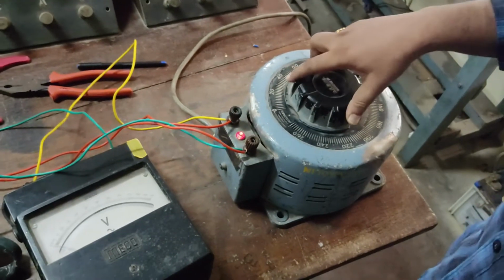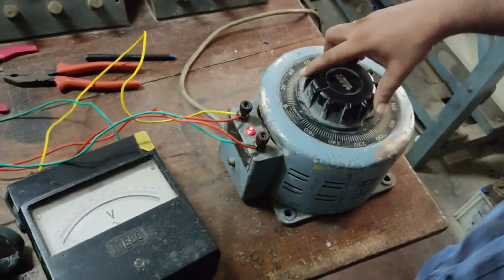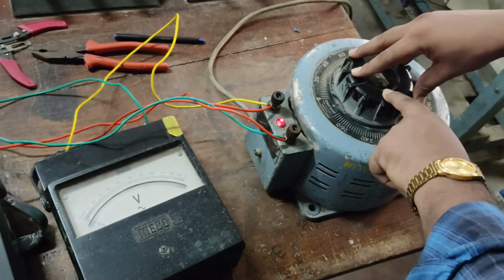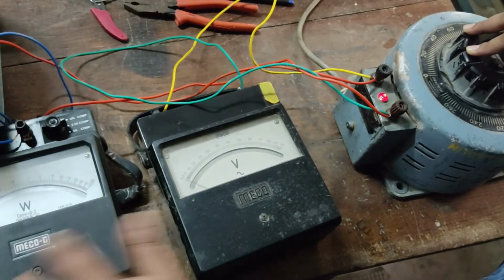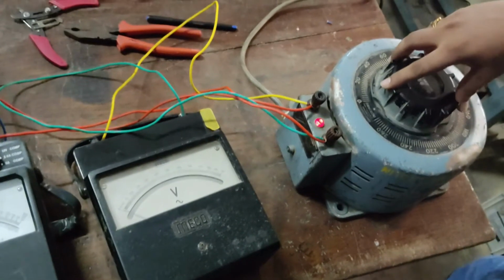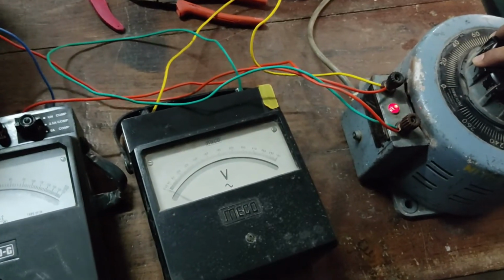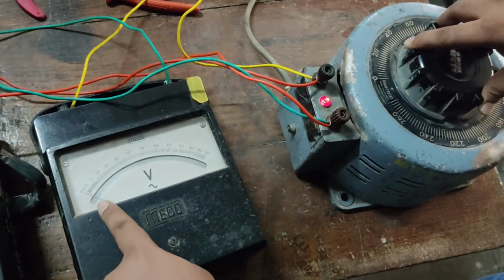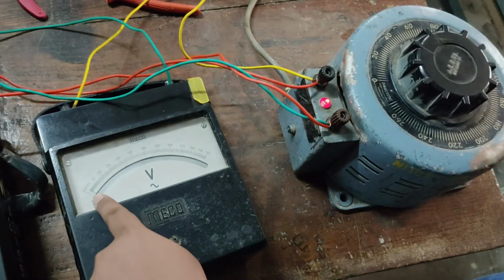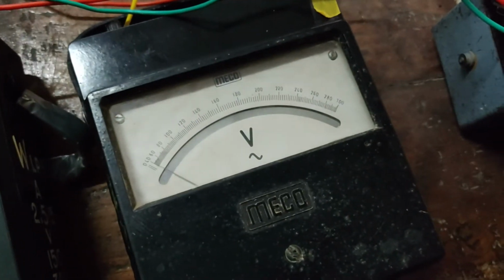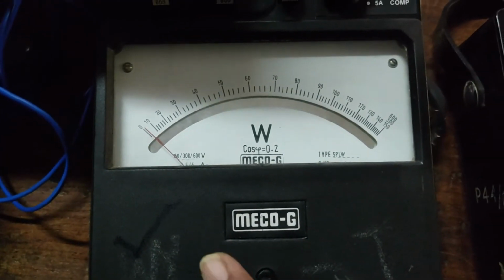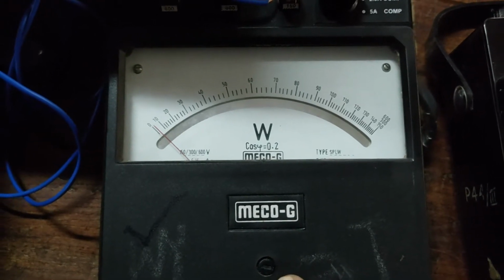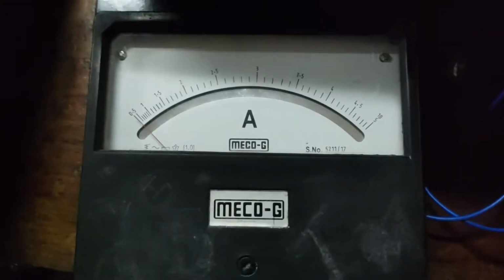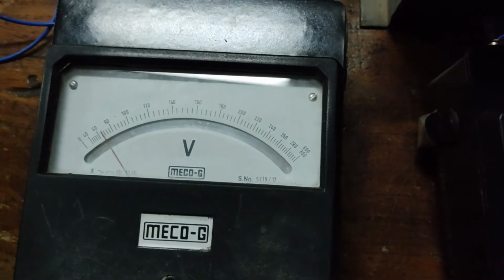So now we'll give the supply and start our OC test on a single phase transformer. With this variac we have to give a supply voltage up to 115. Slowly I can vary this supply, and the deflection will happen in these meters also: ammeter, voltmeter, wattmeter, and output voltage. Now whenever I vary this variac, the input voltage is changing. Now it is 40 volts, but we didn't get any deflection because it is a no load condition. You have not connected any load, that's why we measure the no load power factor. Some voltage we are getting, but current and power require some more voltage, because at no load the current is only about 6% of the full load current.